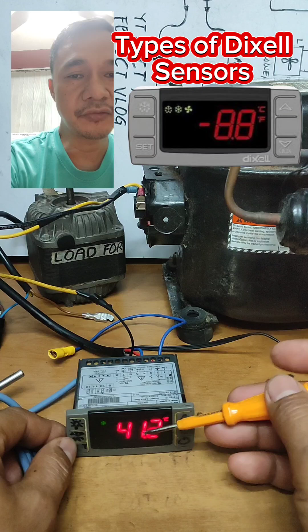Let's check what is the temperature now. We have 41.2, and I'm going to access the calibration to see if there is a value set for this room calibration, and it's set to 000.